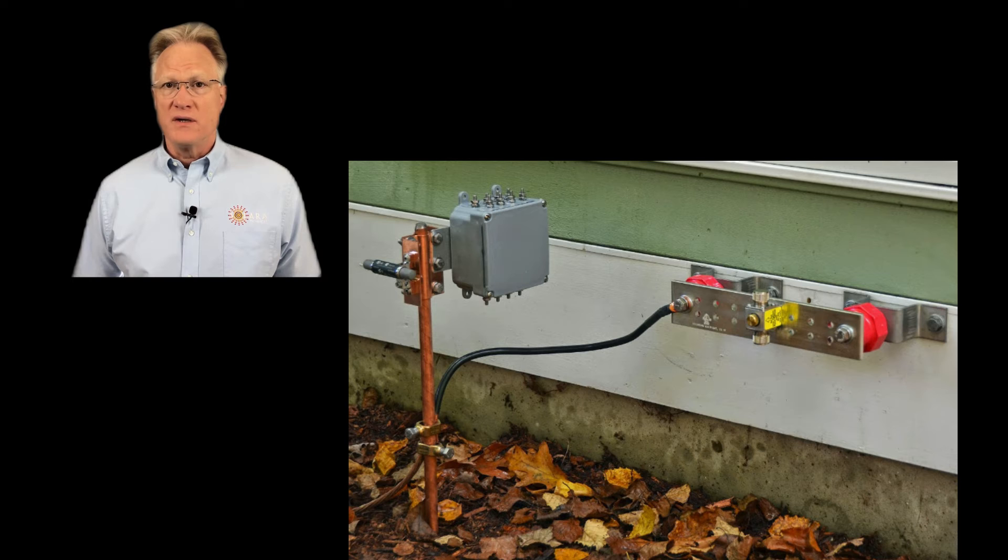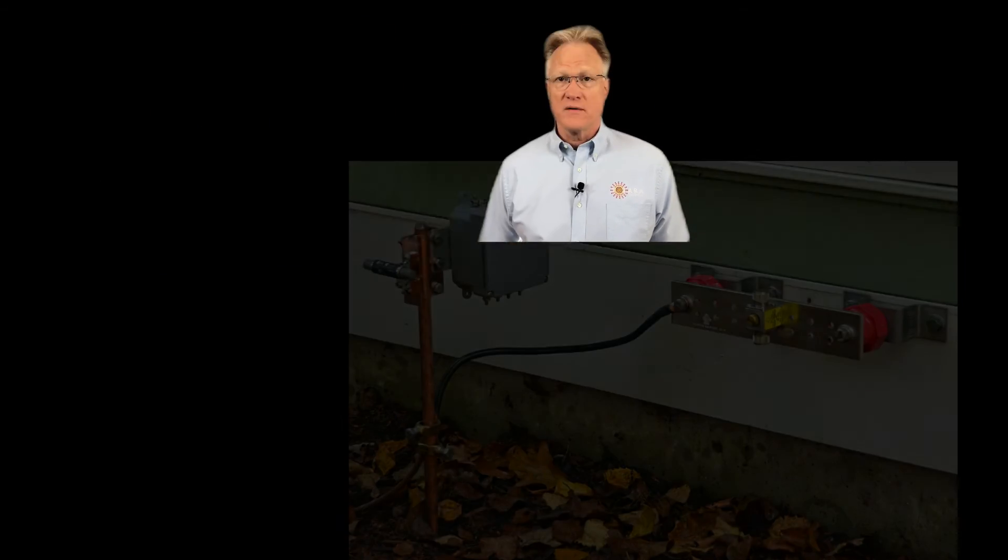Smaller clusters of equipment should have their local power and ground stars, all referenced back to the master star power bar and master star ground bar. Think in terms of islands and sub-islands.